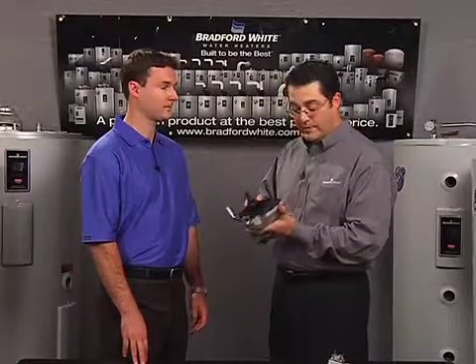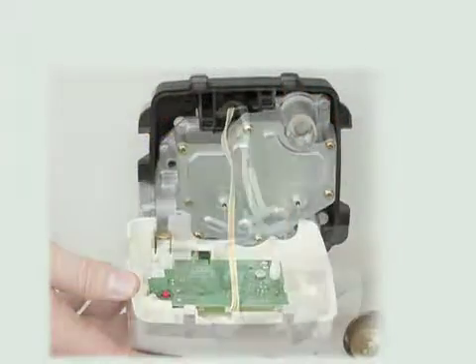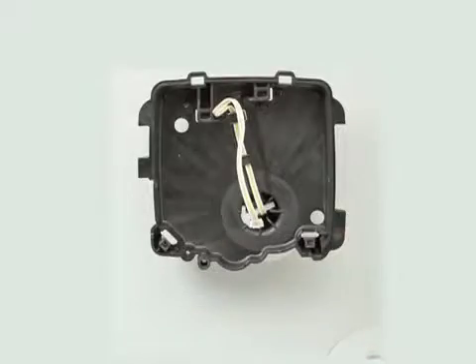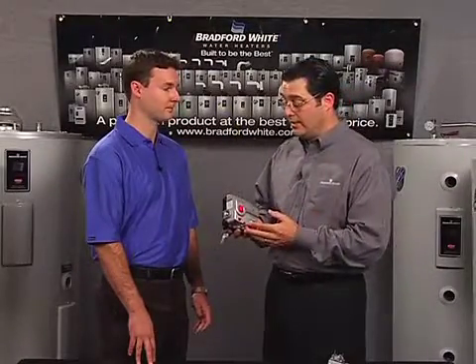Something different about this valve versus a standard water heater valve is that it actually separates — and the thermal well stays inside the tank. That means you don't have to drain the tank to replace or repair the valve. Another huge time-saving feature for the contractor.